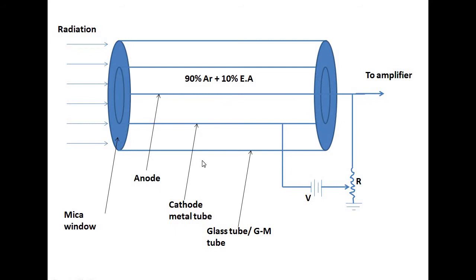This is the schematic of the Geiger-Müller counter. Consider a glass tube, also known as a GM tube, along with the electronic circuit. This electronic circuit is used to amplify the current. Now, this glass tube or GM tube consists of a metal case or metal tube which is enclosed in the glass tube. This metal tube acts as a cathode.